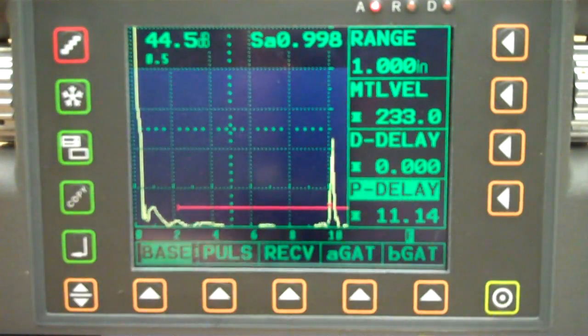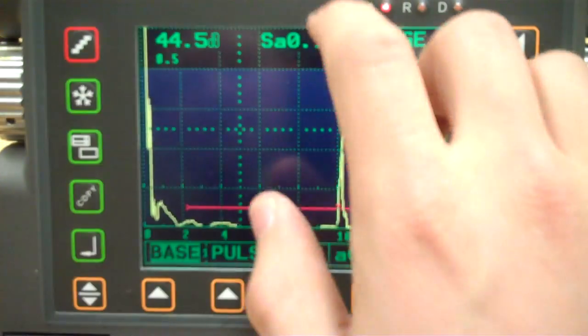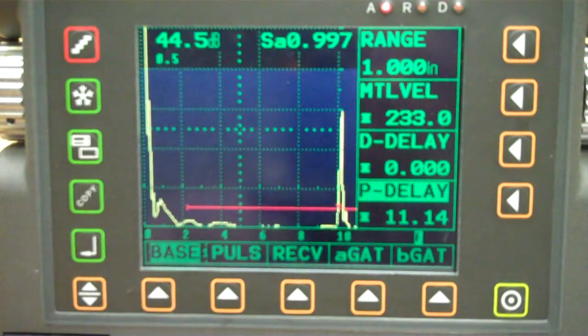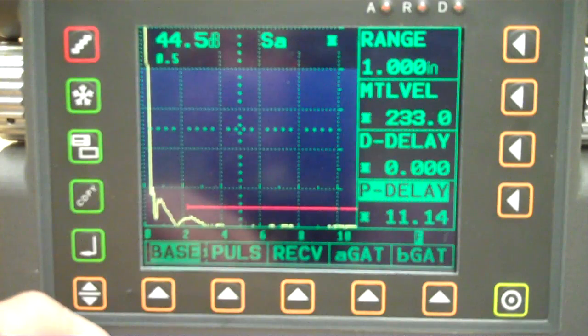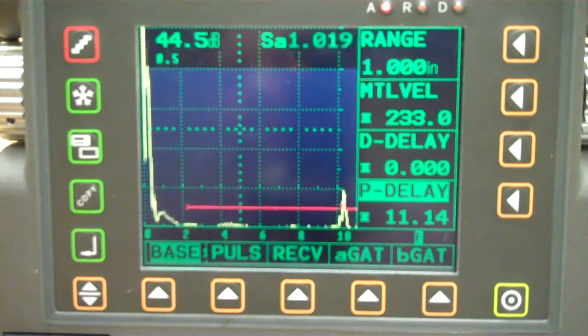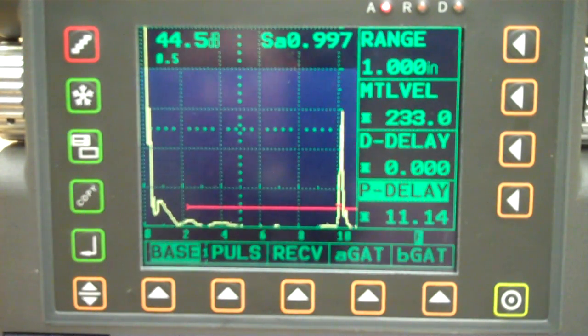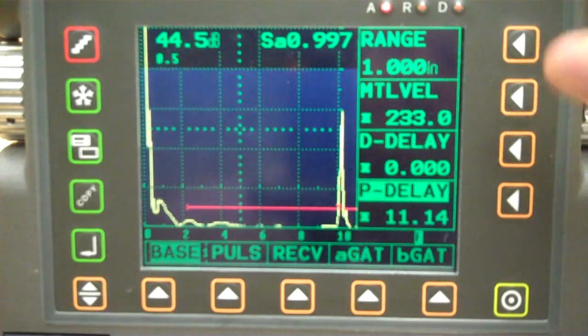Piece of steel. Okay, here's my new 1-inch piece of steel, and you can see that it's giving me a direct readout. There's my 100% line for 1 inch. We're in pretty good shape. So not too bad there. And that's the difference between dual element and single element with a delay line.